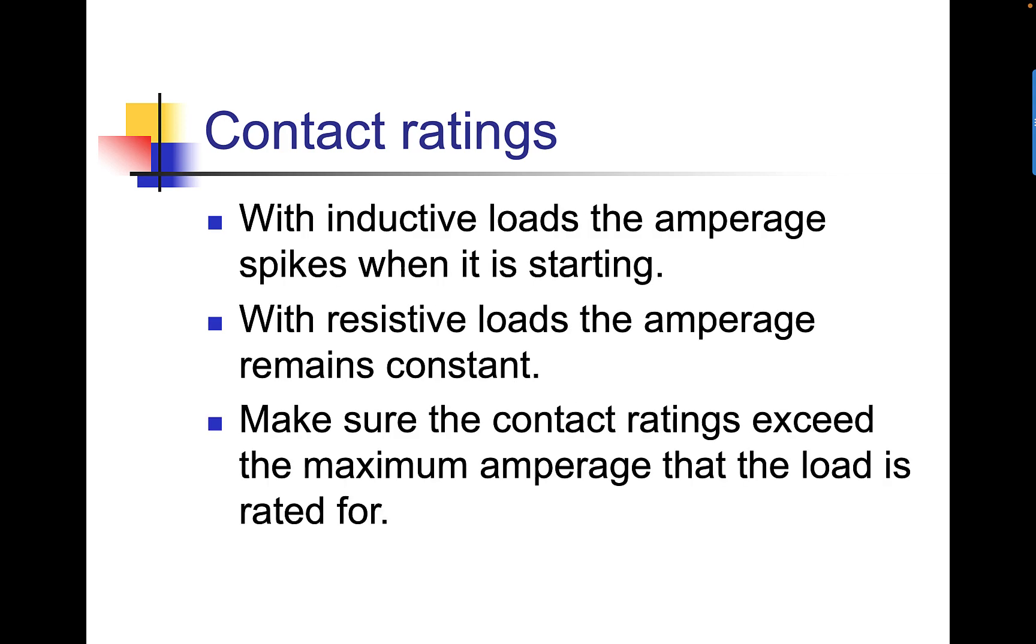With inductive loads, the amperage spikes when it's first starting. With resistive loads, the amperage remains constant. Make sure the contact ratings exceed the maximum amperage that the load is rated for. One size does not fit all, unless it's larger than the maximum amperages on everything you're trying to use it for.